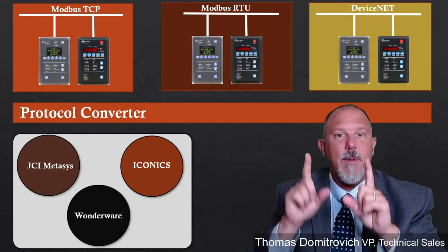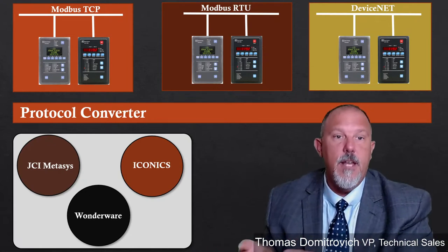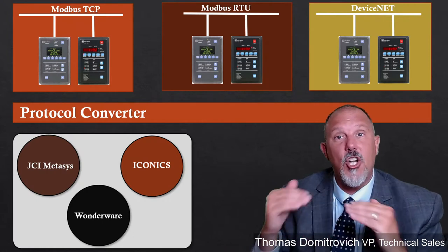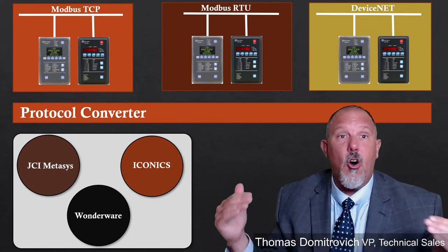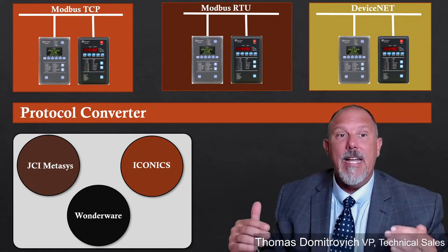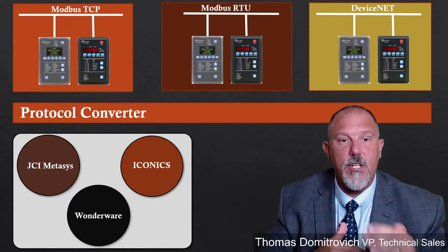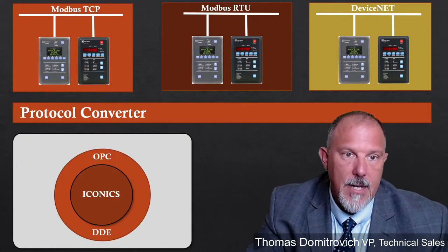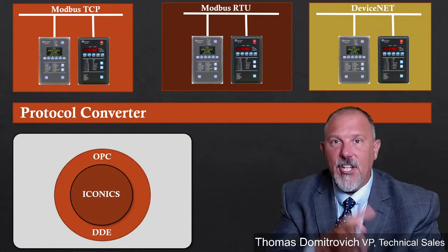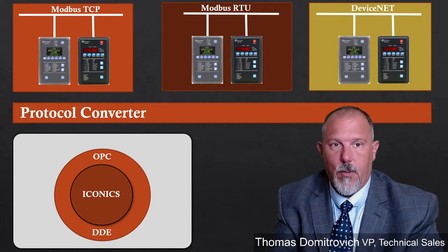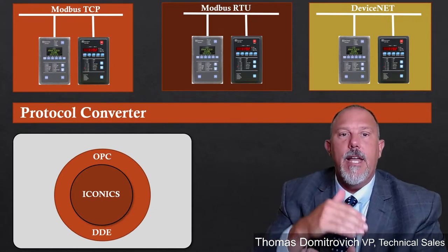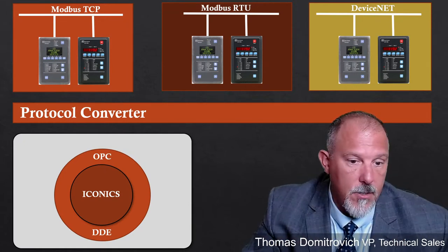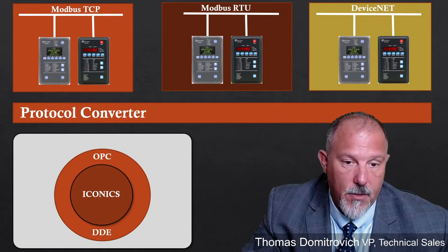Each one of these might have their own protocol converters that take it up to maybe an Ethernet LAN, or maybe it takes it up to one common communication bus that it could all be Modbus, right? I could pull that information into Iconics, Wonderware, or Johnson Controls Metasys system. From an HMI perspective, like Iconics or Wonderware, I could have a driver on my computer, which I did not draw here, but I could draw a driver.